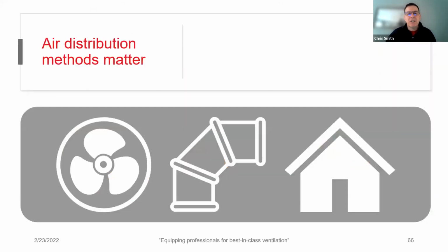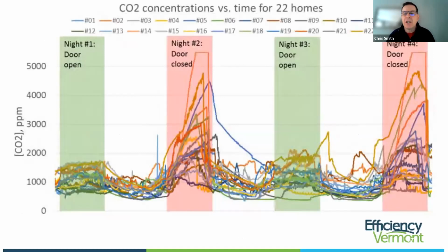It really matters. The method of air distribution really matters quite a bit, because the air quality impact room to room is going to make a huge difference. Here's a study that was done by Brian Just of Efficiency Vermont. I believe this was done back in 2015 or 16. So 22 Vermont homes evaluated for a period of 4 nights in the dead of winter sometime. And basically they're measuring CO2 for a period of 4 days.